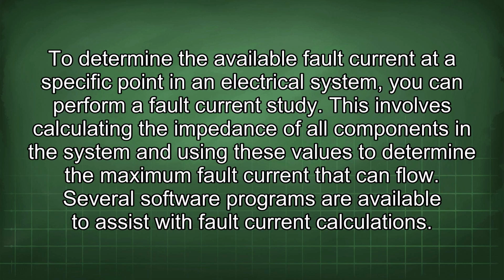To determine the available fault current at a specific point in an electrical system, you can perform a fault current study. This involves calculating the impedance of all components in a system and using these values to determine the maximum fault current that can flow. Several software programs are available to assist with fault current calculations.